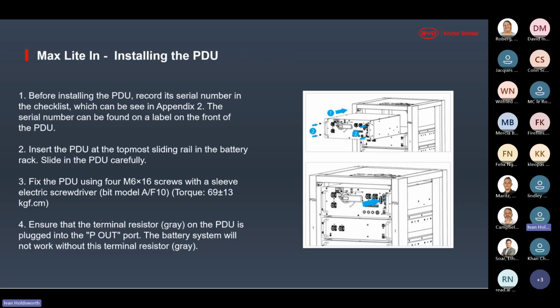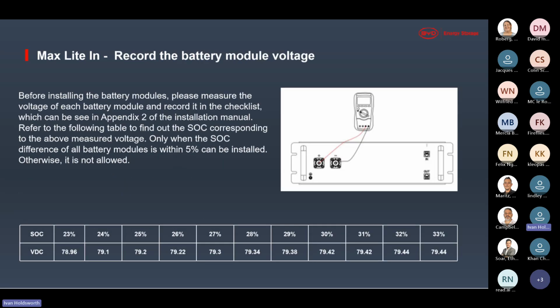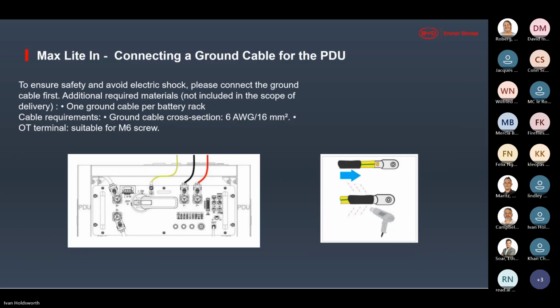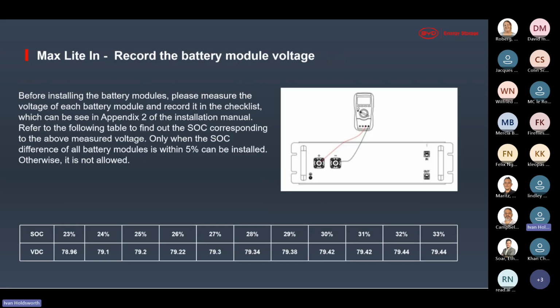And here we can see the installation of your PDU and the measuring of your module voltage, just to make sure that all the modules are at the same SOC when installing. If there is an SOC imbalance, it can take a long time for the modules to self-balance, because they can only discharge a certain amount over a certain time. So it takes a long time to automatically sort out an SOC balance between modules. If the modules are installed all at the same SOC, then there's no problems.